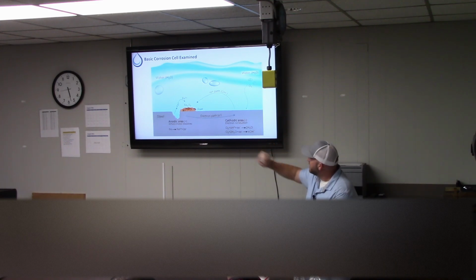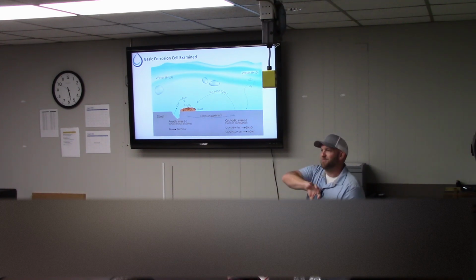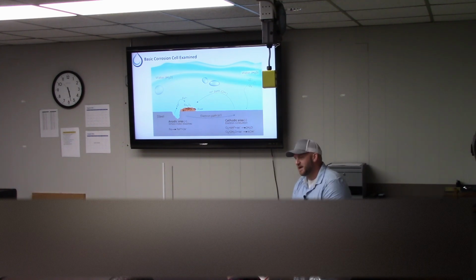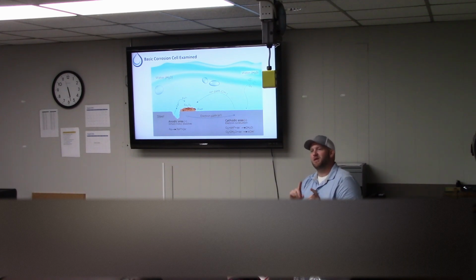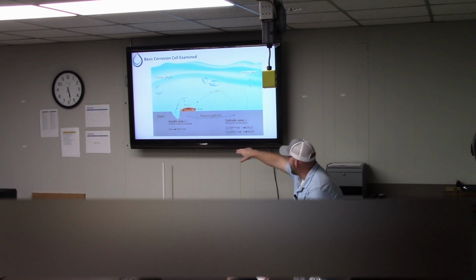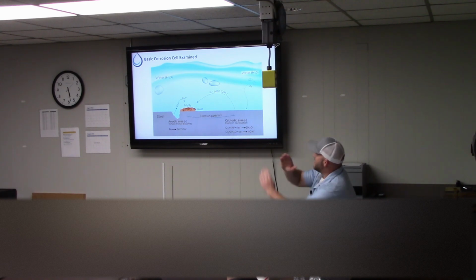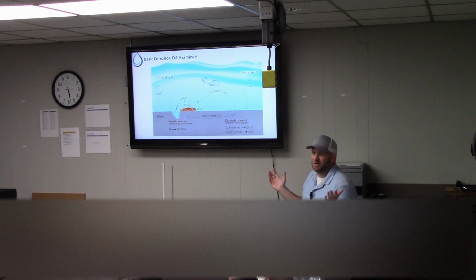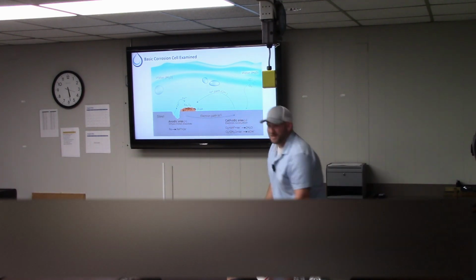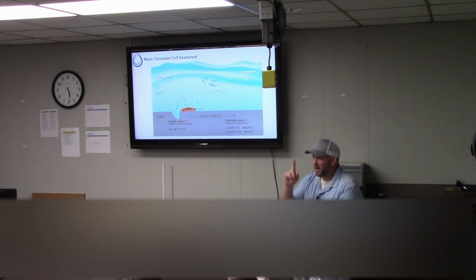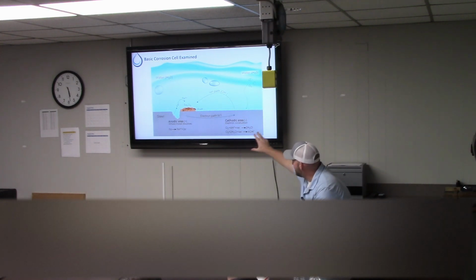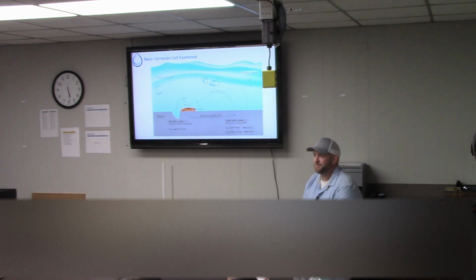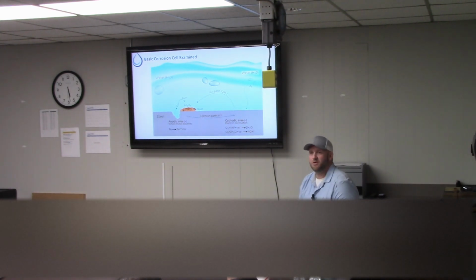It's also good to point out that metal dissolves always at the anode, and it deposits at the site of the cathode. Why is that significant? It's significant because when we get to the point where we chemically treat to stop corrosion, we have to block the anode and the cathode so that we can reduce that corrosion potential. We can't get rid of the water, kind of handcuffed. The cooling tower needs water. This electron path is going to exist. It's got to move. But what we can inhibit is the anodic area and the cathodic area from wanting to corrode. Knowing that it still might happen, you might find that you have sacrificial anodes.